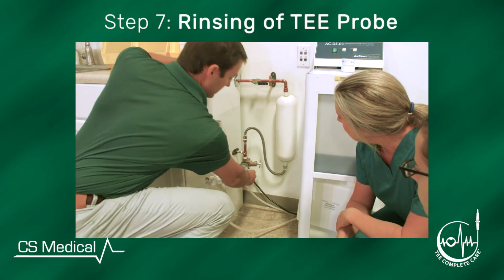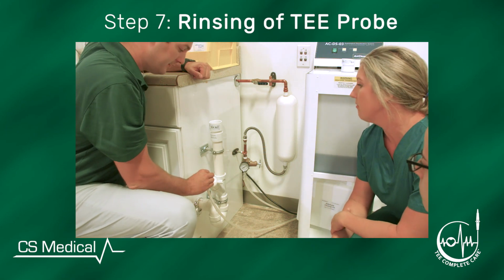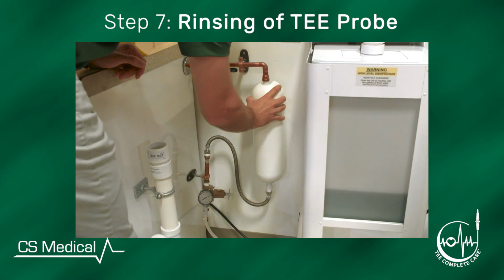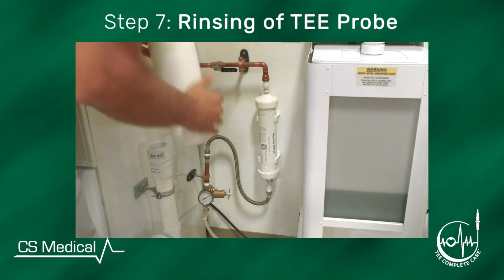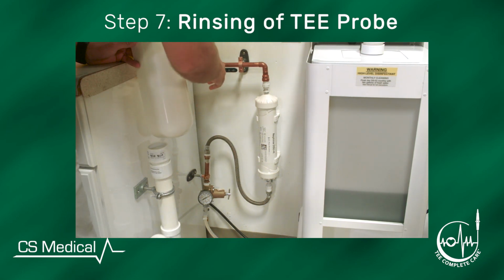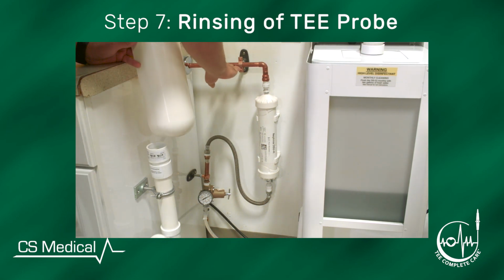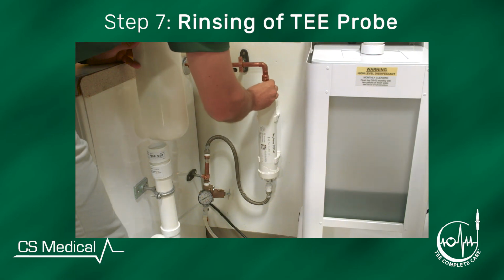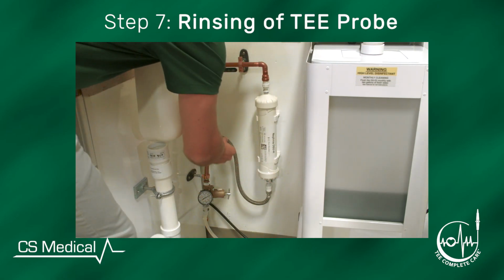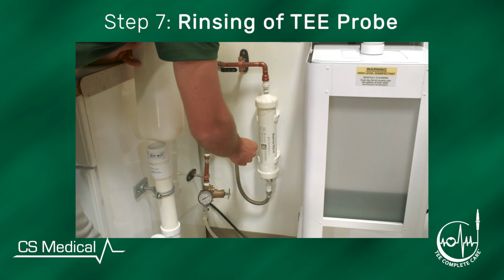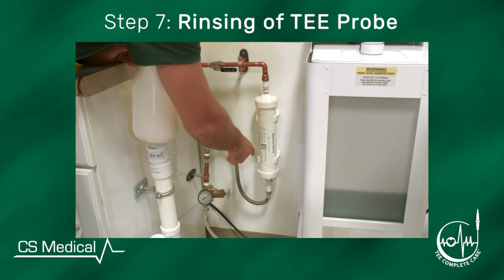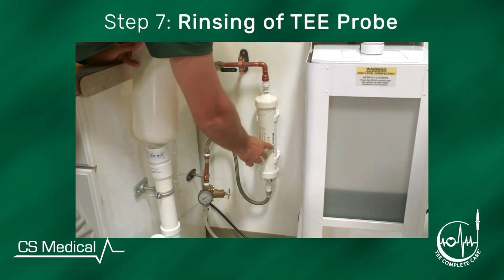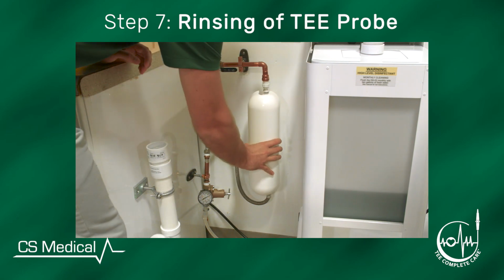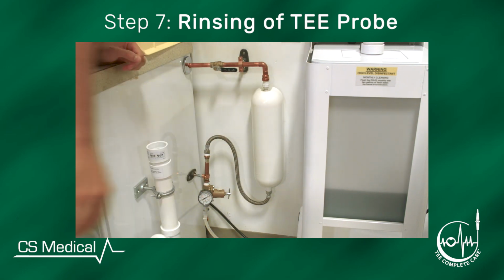Step 7. Rinsing of the TEE probe is required to remove any residual high-level disinfectant. The TD100 only requires the use of high-quality potable water to perform this step in the reprocessing of the TEE probe. In the event your facility has a questionable water source, the Nephros Ultrafilter is an FDA-cleared medical device that offers 5 nanometer water filtration and removes potential hazards found in your water supply.